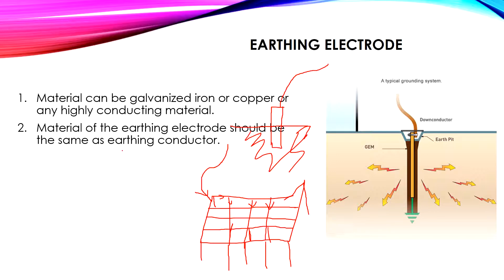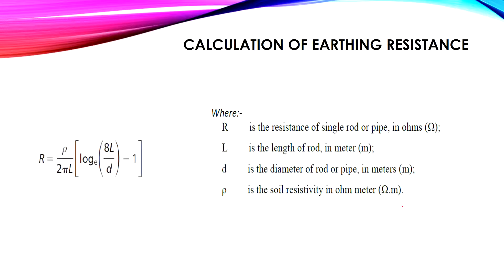The material of the earthing electrode should be the same as the earthing conductor — meaning the conductor, the earthing electrode, and the conductors in the grid should all have the same material. This is to prevent corrosion caused by connecting different materials, which produces a potential difference between them. For example, galvanized iron and copper have different potentials, which causes corrosion of one of the conductors or the earthing electrode.